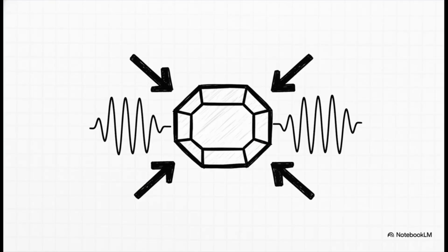Here's the magic: inside the sensor there's a tiny quartz crystal vibrating, or humming, at a super precise frequency. When pressure from the well starts to squeeze it, that frequency changes. It's so sensitive that even the tiniest, almost unnoticeable change in pressure creates a change in vibration that we can measure, and that's what gives it that crazy high resolution we were talking about.